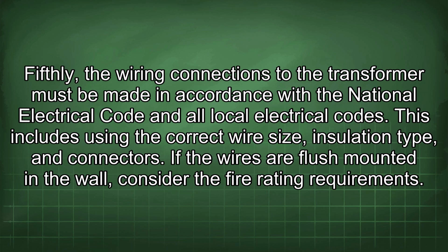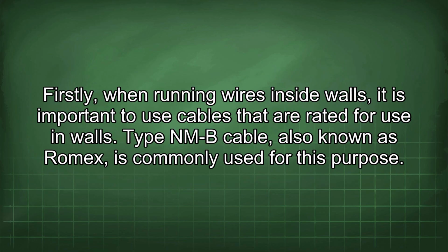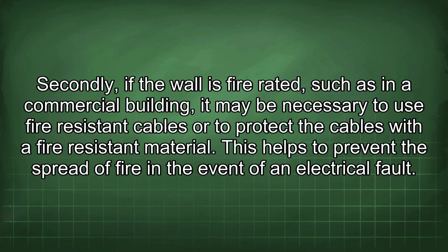If the wires are flush mounted in the wall, consider the fire rating requirements. Firstly, when running wires inside walls, it is important to use cables that are rated for use in walls. Type NM-B cable, also known as Romex, is commonly used for this purpose. Secondly, if the wall is fire rated, such as in a commercial building, it may be necessary to use fire-resistant cables or to protect the cables with a fire-resistant material. This helps to prevent the spread of fire in the event of an electrical fault.